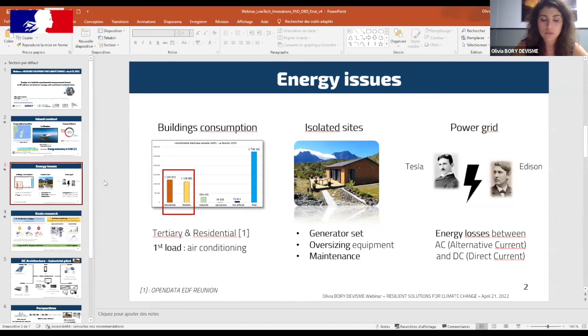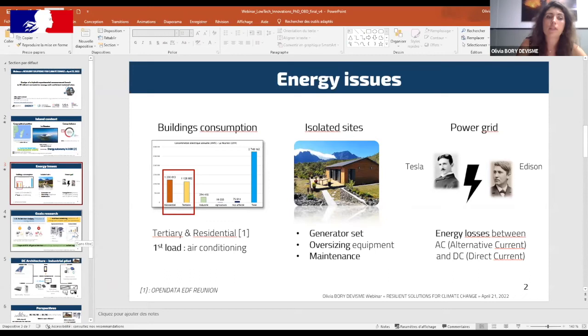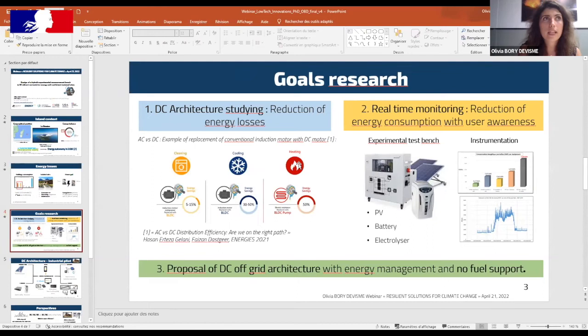With the insertion of renewable energy into the grid, a debate is growing between alternative current and direct current. To use solar energy we need many converters between solar panels and our equipment: first we convert direct current to alternative current for our grid, then we convert it a second time for DC equipment like LEDs, screens, computers, data centers, and some motors. This is not optimal and creates a lot of energy losses. Currently we don't know exactly how to quantify the energy savings possible with DC current, which is why my research goals focus on developing new DC architectures to reduce energy losses linked to converters and electrical transport.